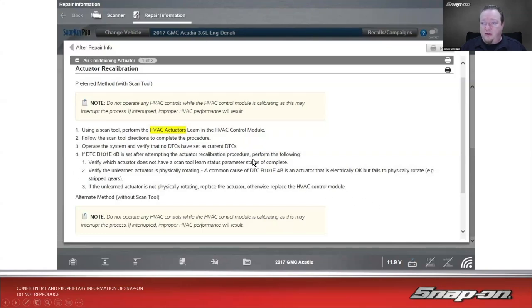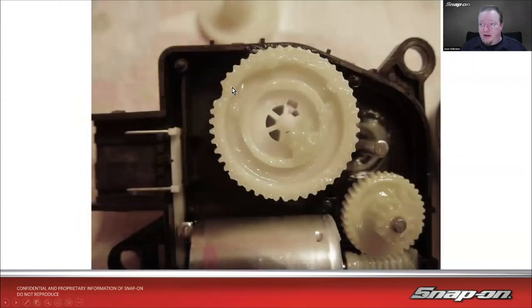So we can see which ones do work and do not work. And oftentimes when they don't work, it's because of something like this - maybe it got stuck at one point and ended up stripping this gear right here. We can see where that would be flipped over, and then we'd have the gear right there as to where that would be. It may strip it, and then I'd have to either replace the gear, repair the gear, or most times you're probably just going to replace the actuator. See how I have a worm gear here and a reduction gear.